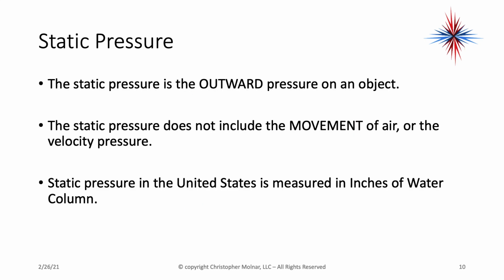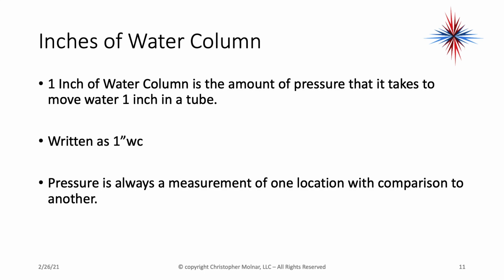A static pressure is the outward pressure on an object. A static pressure does not include movement of air, otherwise known as the velocity pressure. Static pressure in the United States is measured in inches of water column. Other countries that use the metric system have other measurements. You'll have to look those up; I'm not going into them here. An inch of water column is the amount of pressure that it takes to move water 1 inch vertically in a tube. It's written as 1 inch WC.